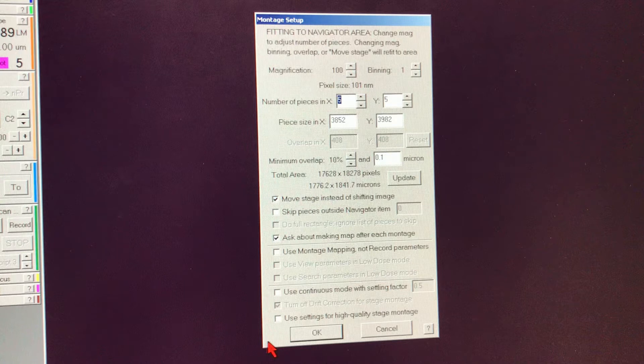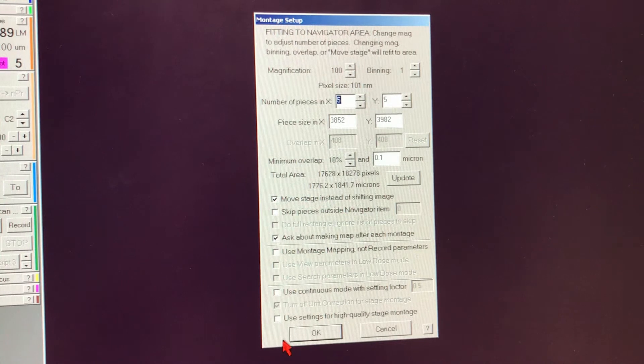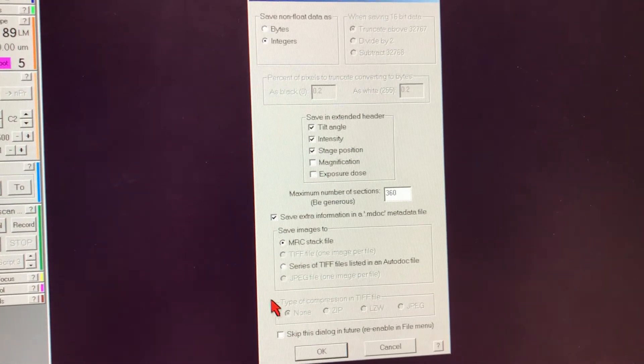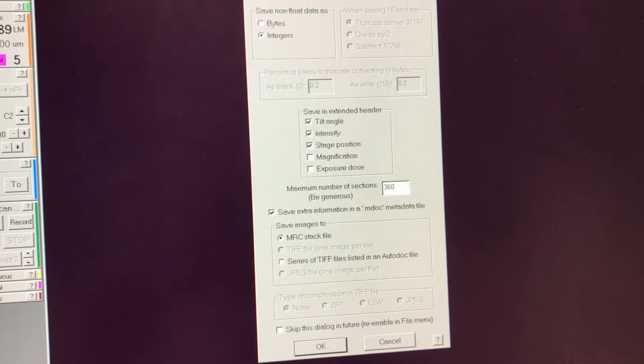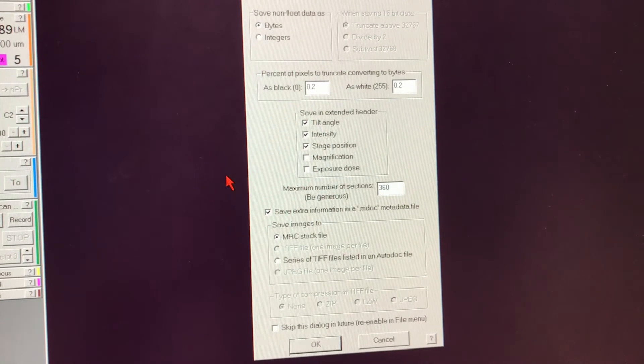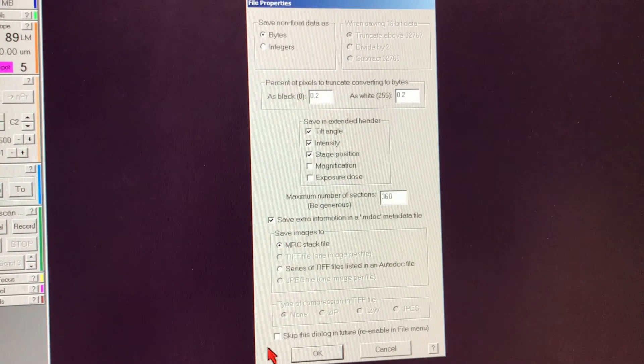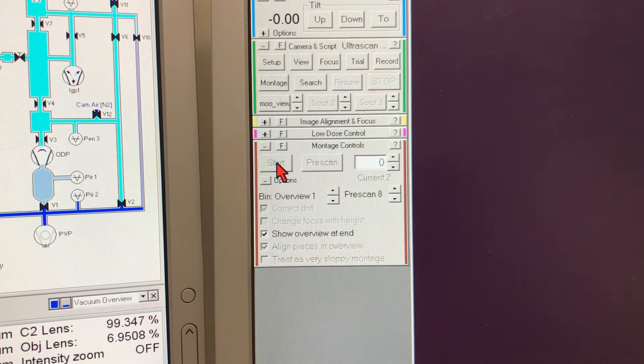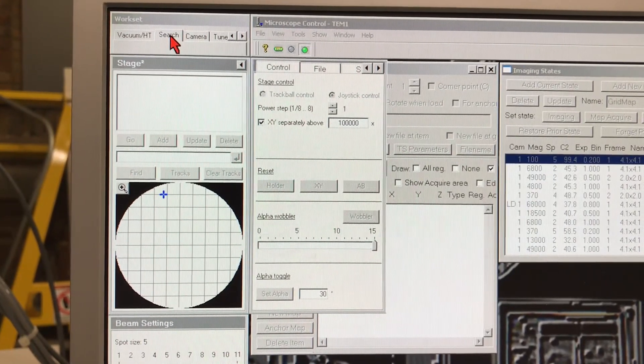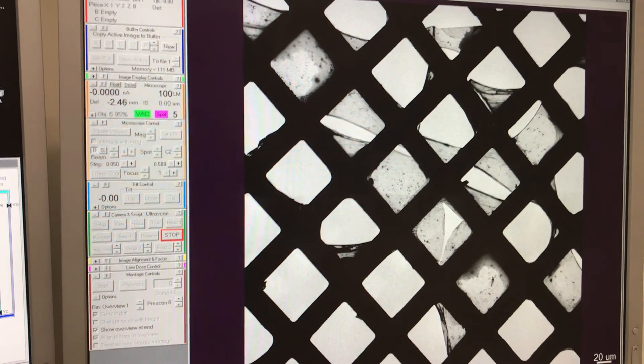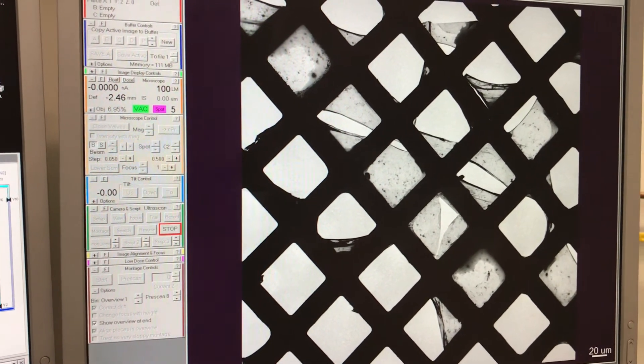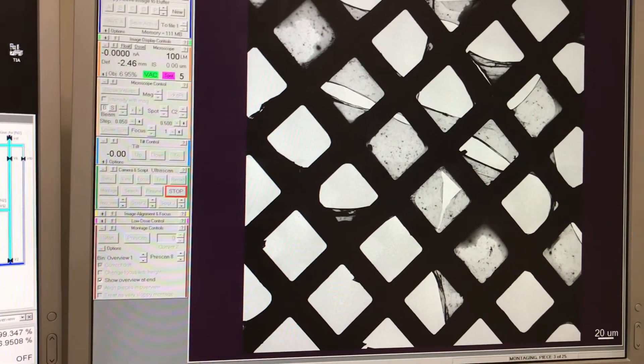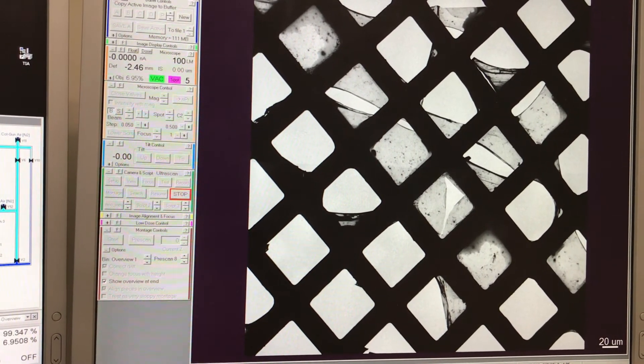We will set up the program to build a map which is made up of 5 by 5, which is 25 pictures, that will span our whole grid. We typically use an MRC file format to save the atlas—it's a very common format to save your micrographs in normal EM or cryo-EM. As soon as you click start for the montage, you can see the stage is now going to move around taking images of each section and stitching up 25 images to build an overview of the grid that we have in the microscope right now.